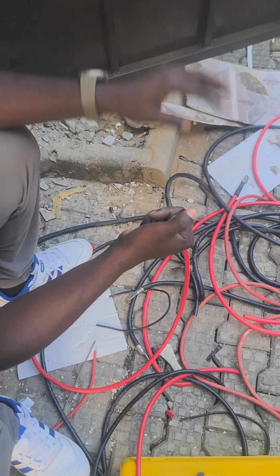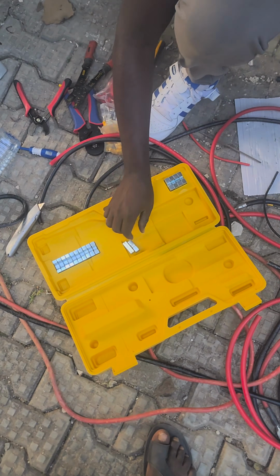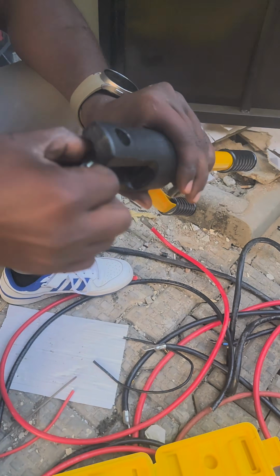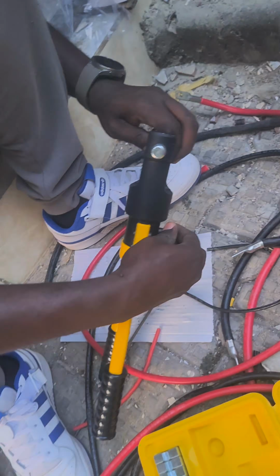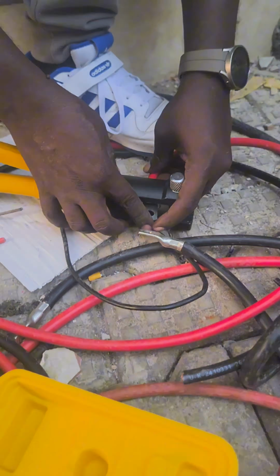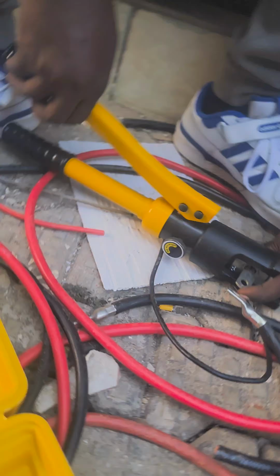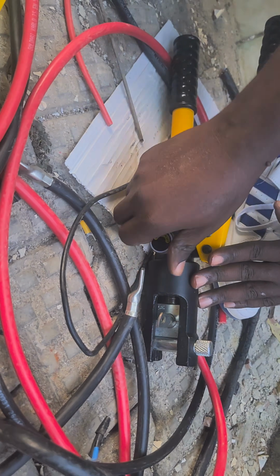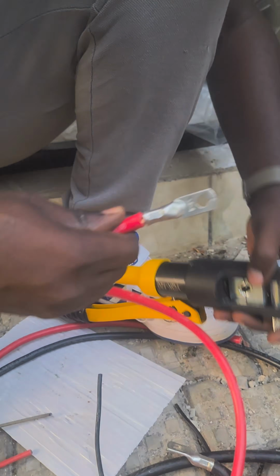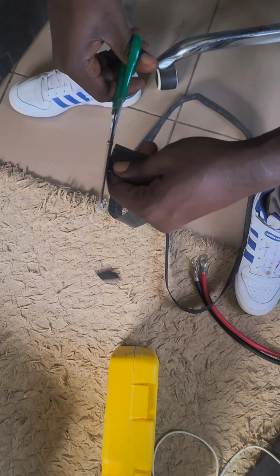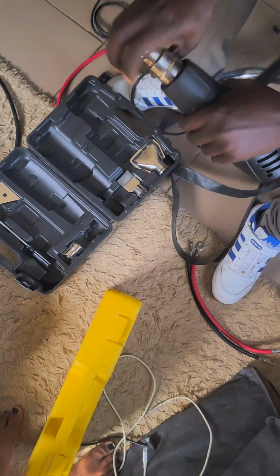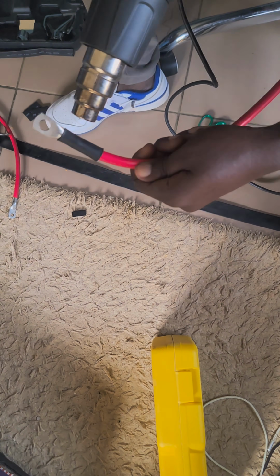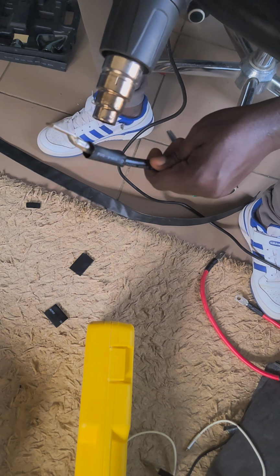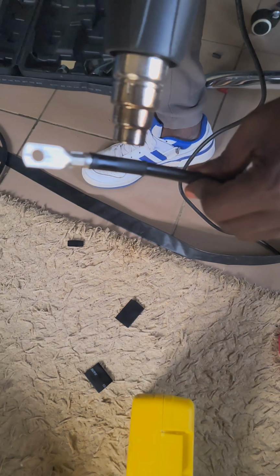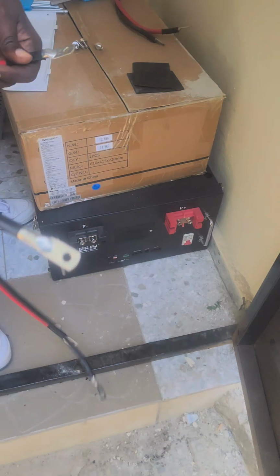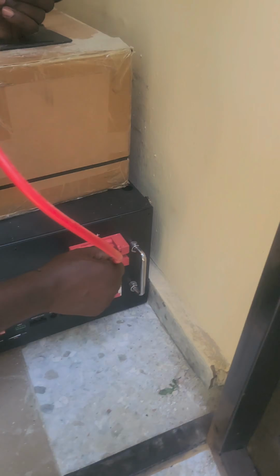So now I'm making the battery cables. I'm using 35 cable between the battery and the inverter. Now I'm just adding cable lugs to those cables. I'm using a hydraulic crimp to make sure that those cable lugs are tight and installed properly on the cables. Here I'm using heat shrink. I'm using my heat gun to shrink the heat shrink over the part where the lugs touch the cable. This protects the inner wires from things like moisture and makes sure there's no exposed wire essentially.